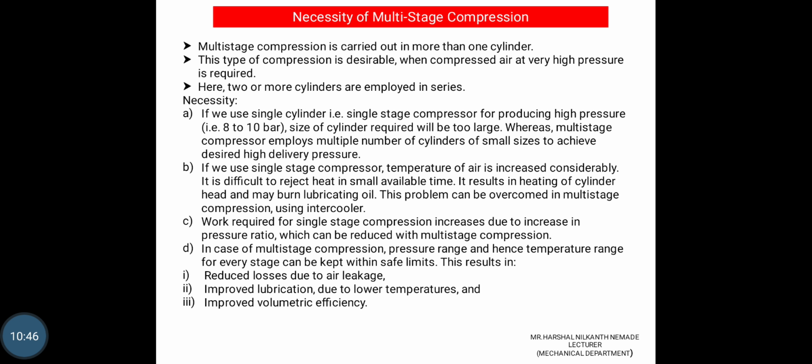Work required for a single stage compressor increases due to the increase in the pressure ratio, which can be reduced by the multi-stage compressor. In case of multi-stage compression, the pressure range and hence the temperature range for every stage can be kept within a safe limit. This results in reduced loss due to air leakage, improved lubrication due to the lower temperature, and improved volumetric efficiency.